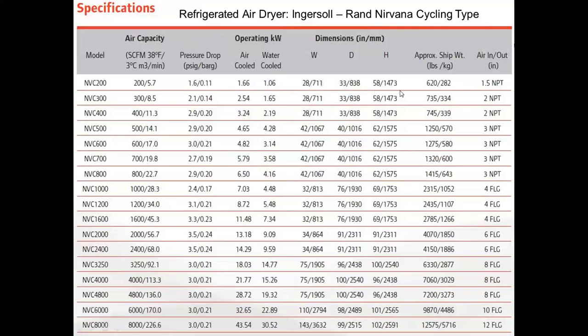So anyway, dimensions, shipping weight, and just the size of the connection where the pipes connect in. And we see, gosh, we got a big guy down here at 8,000 CFM. And so you can compare and contrast. But remember this 500, this would nominally be what we would put with a 100 horsepower compressor, because we're between 400 and 500 CFM. So that would be the unit for that. If we say 20 kW per 100, then for 500 nominally, 5 times 20 would be 100 kW on the compressor. And so the dryer is going to add another 4 to 5 kW in this case. And we'll talk about the desiccant later.